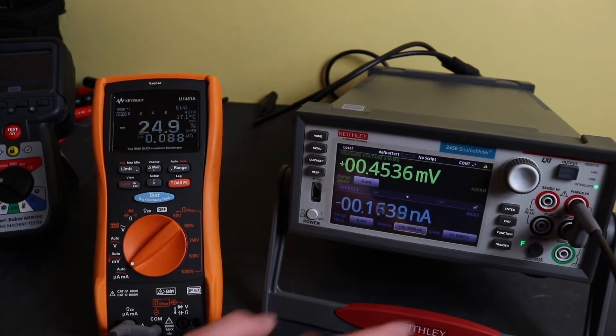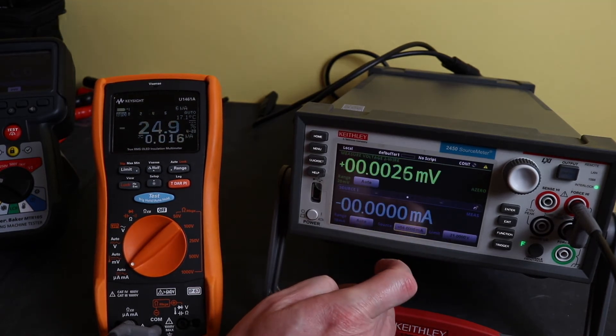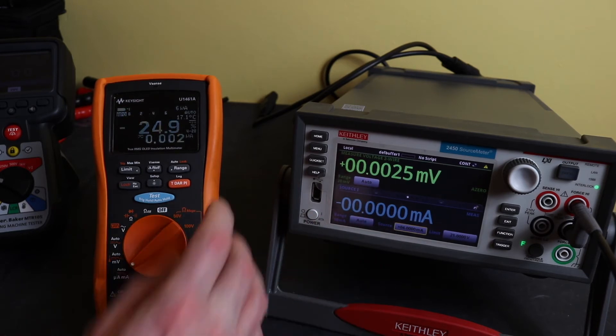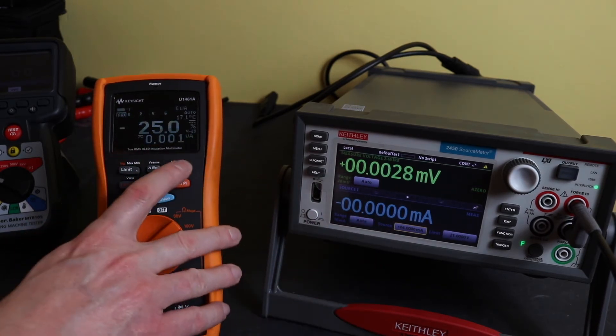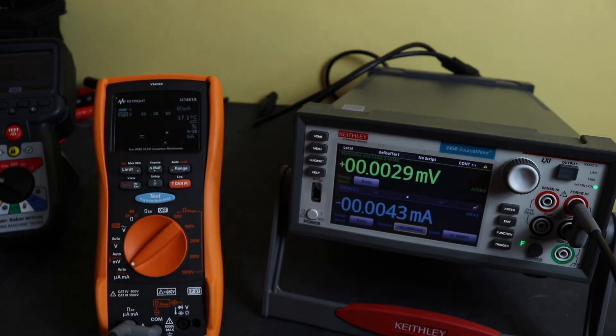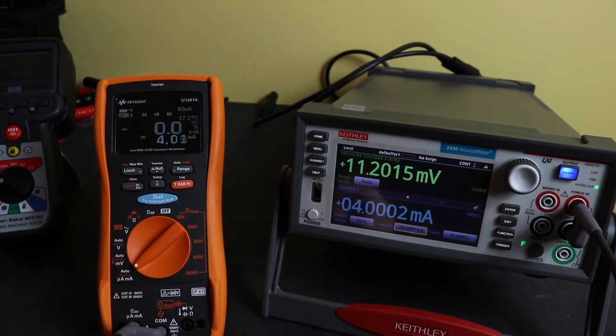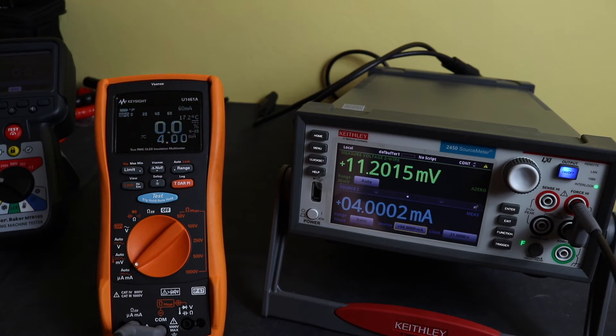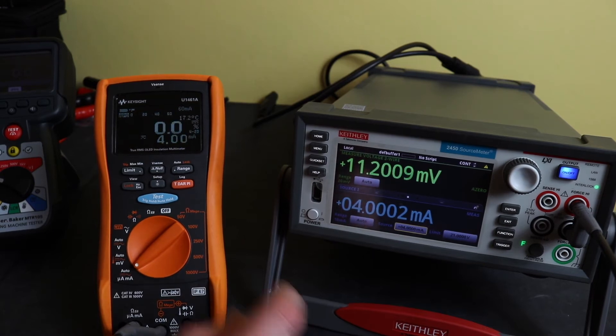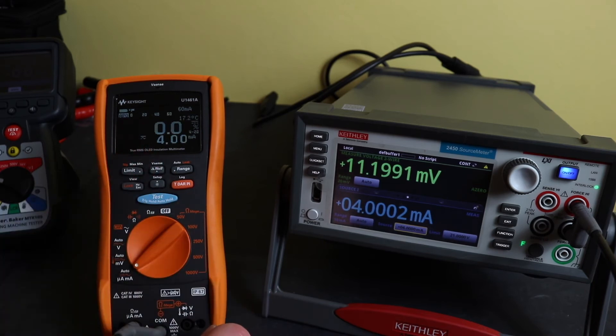Okay so we've set up our source measurement unit and I'll set them to supply four milliamps. I've got my Keysight setup here. I'm just going to change the range on that so that it stays on milliamps. It just makes it a little bit quicker test to say changing the ranges as we go on and we'll put four milliamp in and then hopefully you can see there we've got four milliamp down at the bottom 4.00 and we've got zero point zero percent.